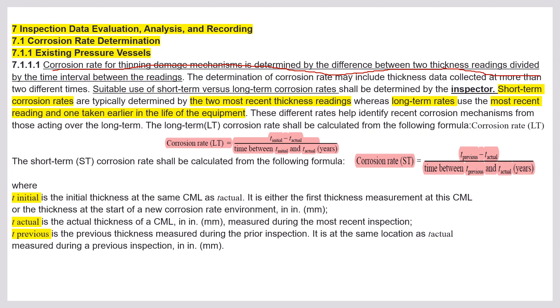For example, the initial thickness was 20 mm. After five years you find it became 15 mm. In five years it lost 5 mm, so every year it loses 1 mm. That 1 mm per year is the corrosion rate. Based on that corrosion rate we find the remaining life. If 1 mm is corroded per year and there is still 15 mm remaining, within 15 years all will be damaged.